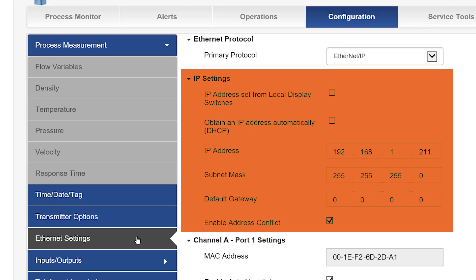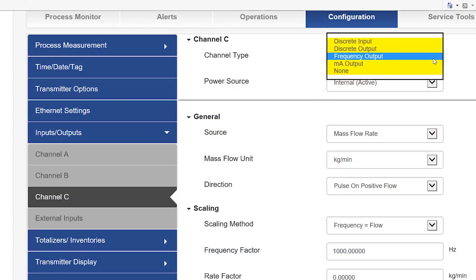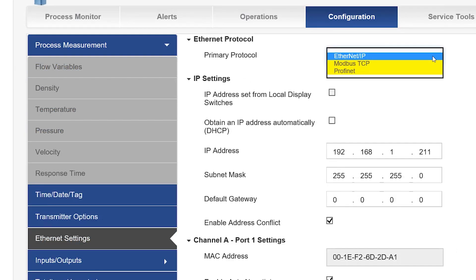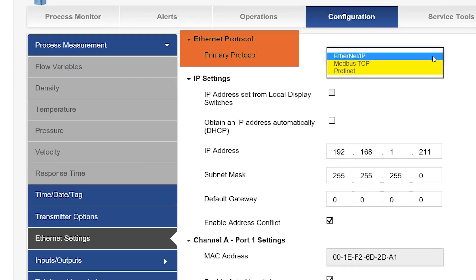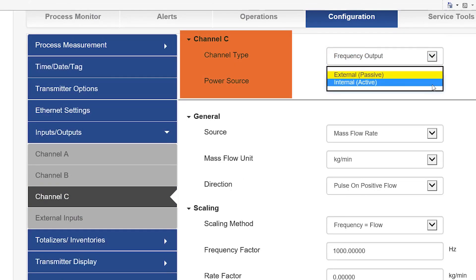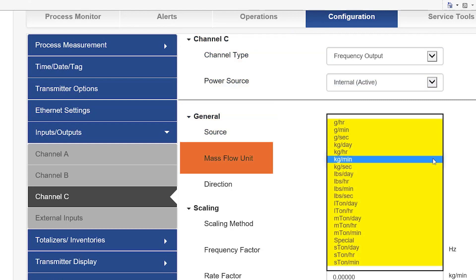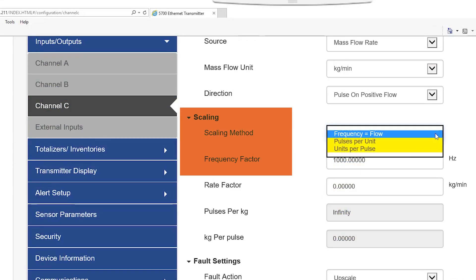The IP settings for the transmitter can be configured to match the user's network settings. The inputs and outputs settings allow the user to change the channel type for channel C as a discrete input, discrete output, frequency output, milliamp output, or set to none. Channel A and B are configured by setting the Ethernet protocol, which is found in the Ethernet settings menu. Power source for channel C can be changed as passive or active. Source, flow units, and frequency scaling can be configured depending on the channel type selected for channel C.